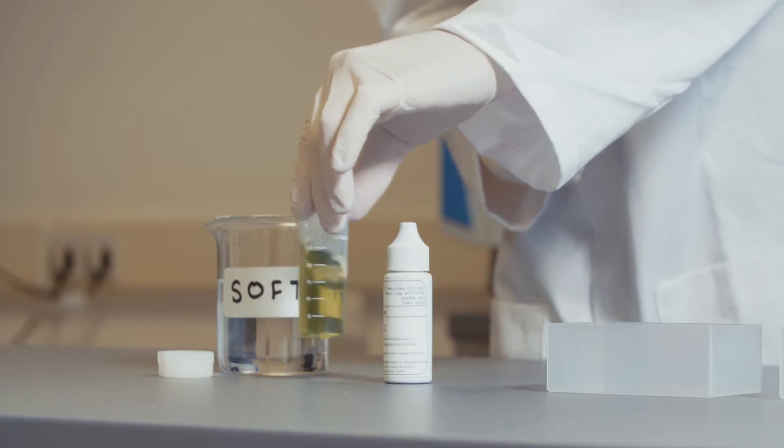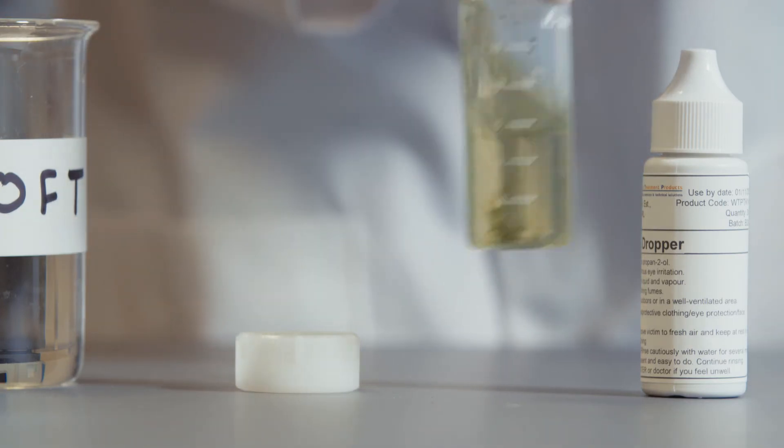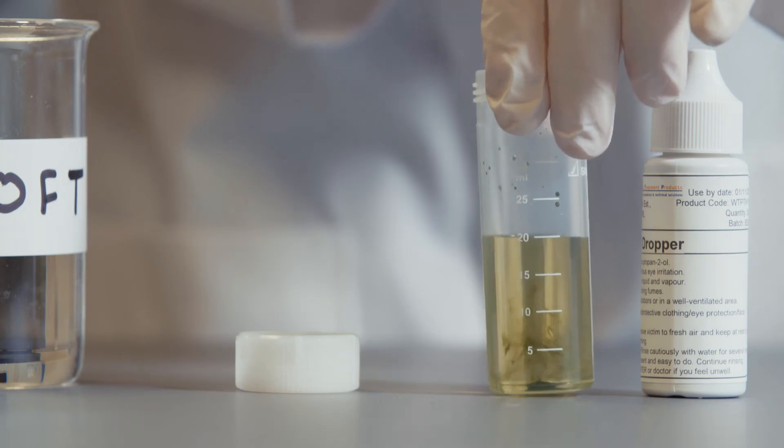Swirl the sample pot to mix the indicator thoroughly. A green color indicates the sample contains less than 10 ppm of hardness.